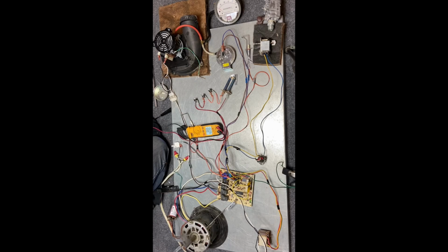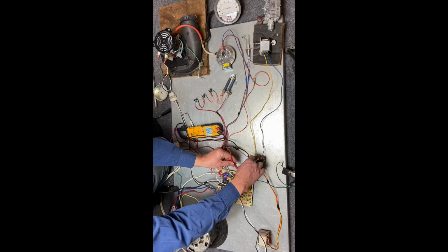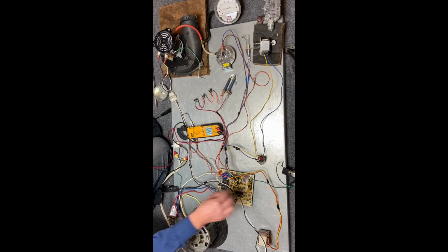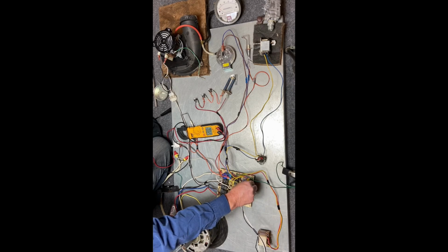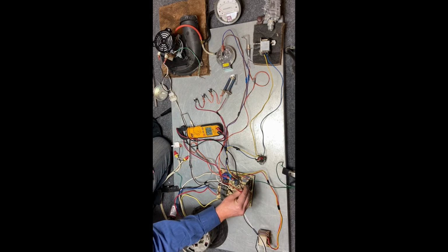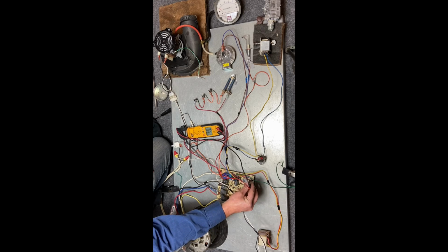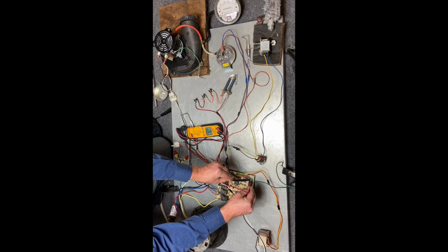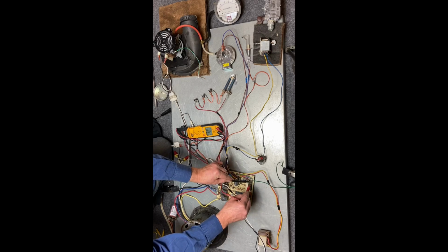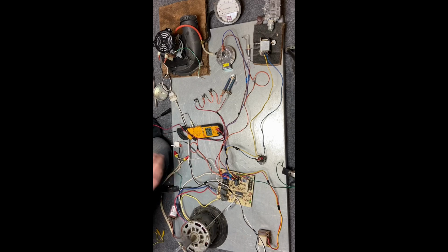Now to our transformer, the same way we checked it, we see that we have voltage coming to our transformer. And we have 121 volts going to our transformer. Then we check our secondary voltage coming out of the transformer. And we have 27 volts coming out of the transformer. But we can also check that same voltage with these terminals on our fan relay. If I check between R and C, we end up showing 27 volts. And I can check between R and any of the other terminals, even though it's not calling, there's a potential 27 volts. We have also 27 volts. We have 27 volts. So we have 27 volts between all of those components.